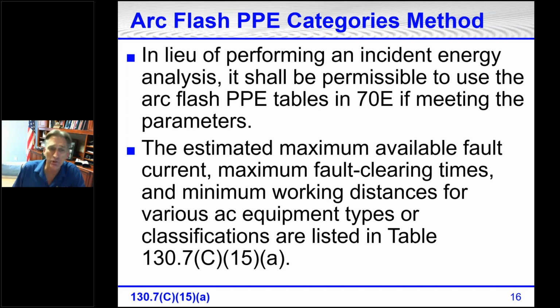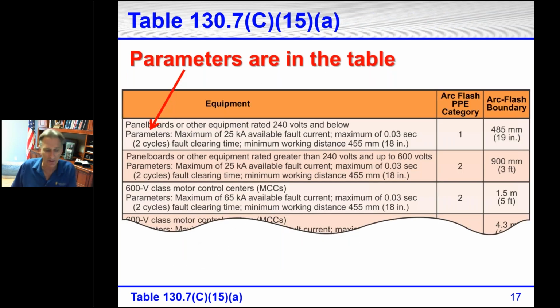Now, these tables have parameters. We have to know the maximum available fault current, the maximum fault clearing times, and the minimum working distance for various equipment. So here's the table, 130.7C15A. The parameters are in this table. The parameters for this one: a maximum of 25,000 available fault current amps, a maximum fault clearing time of 0.03 second or 2 cycles, and a minimum working distance of 18 inches. Now, normally 18 inches is for fixed equipment. 18 inches is typically the working distance, and that's usually figured from the live energized parts to your body when you're holding something like test leads for test instruments or voltage detectors.